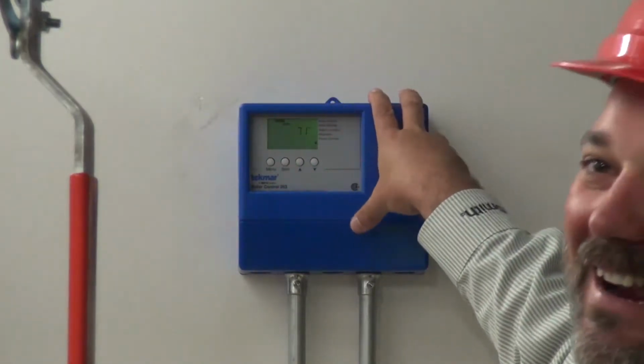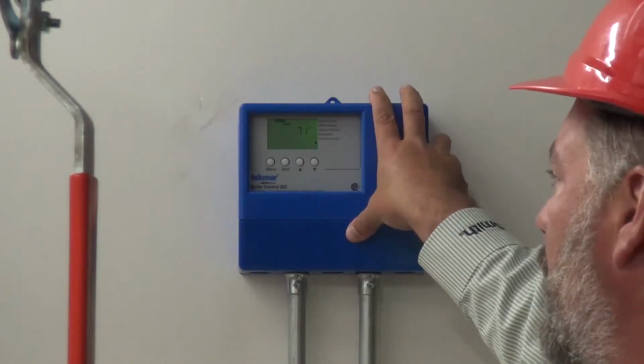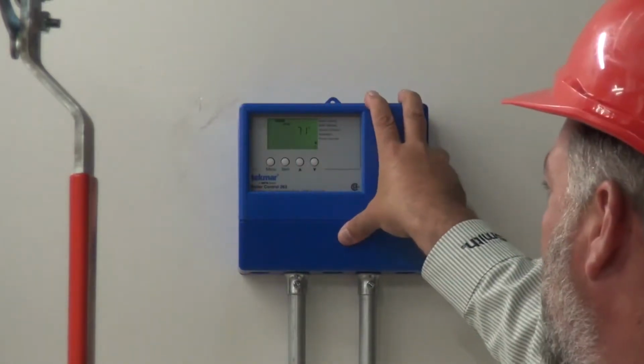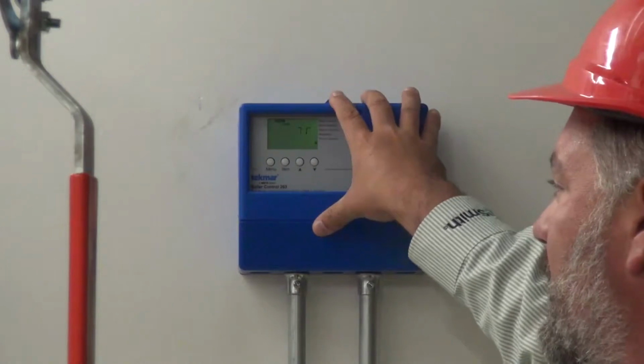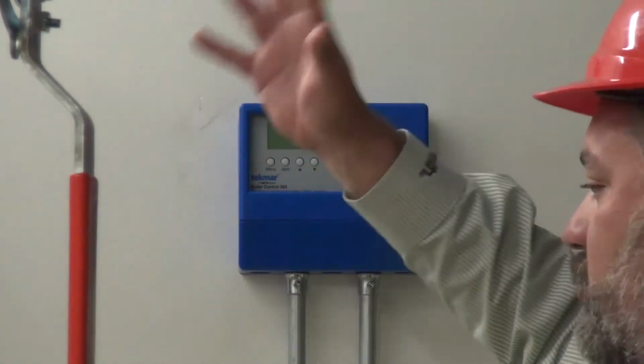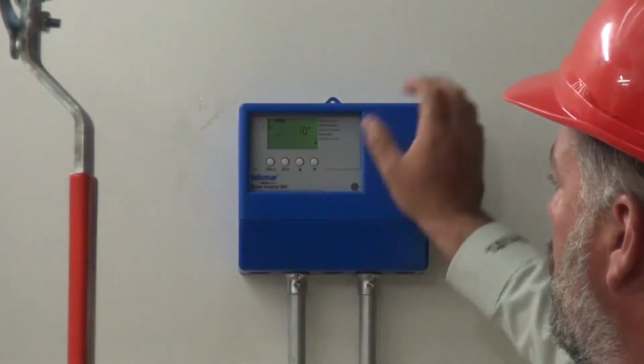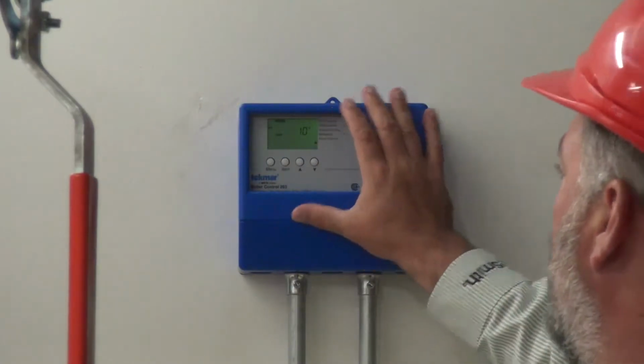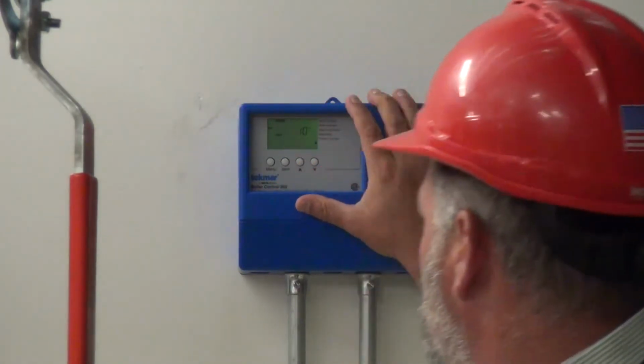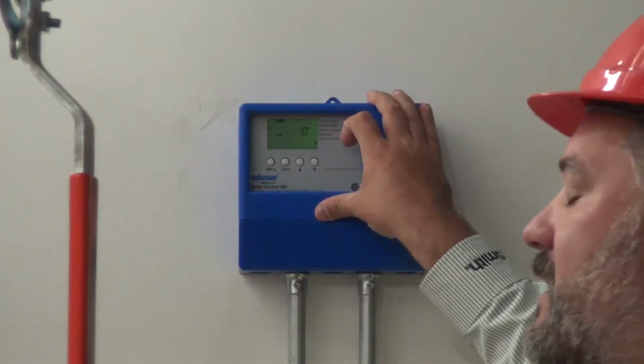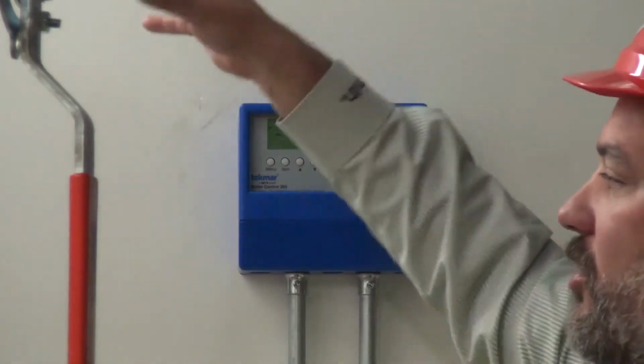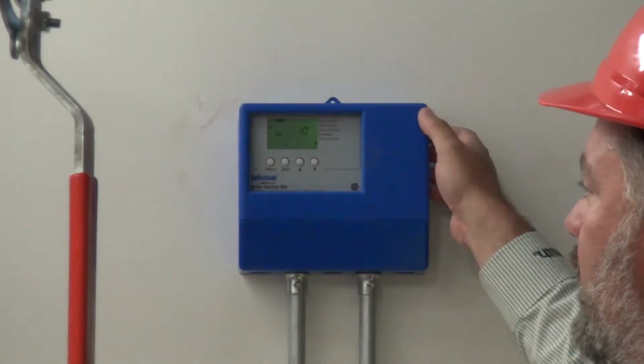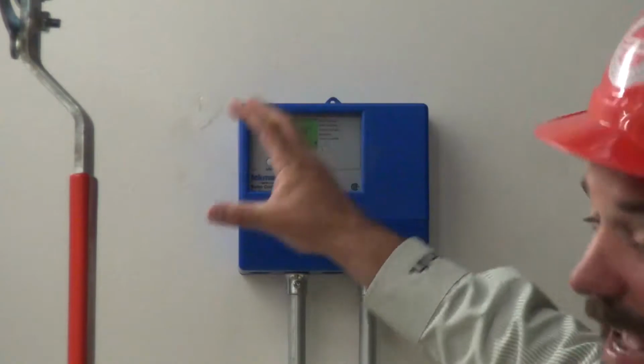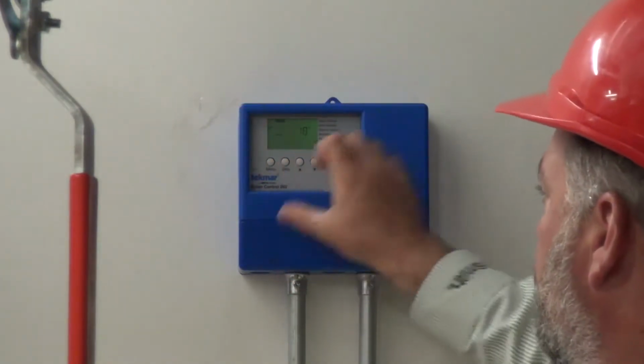Again, we don't really care about that. So it shows 71, but you're not going to mess with that. This doesn't really have any sort of control over our boilers. We'll hit item. Now this is where we're showing again an outdoor reset, and it shows 10 degrees. That's an outdoor reset controller that we don't have the outdoor reset control set up on here. That doesn't matter on here.